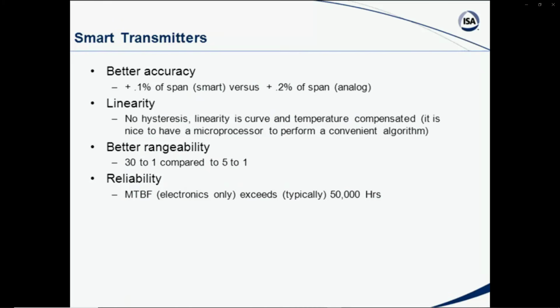At one point in time, we were using the conventional analog transmitters, actually of 1/4, 3/4%, some of them even 1% in some cases, and we were using those and putting that into a highly accurate electronic computer system or some system that had high accuracy. But now with the smart transmitters, we can get even better than 1/10% of span, which is a lot better than the old 1/4 or 1/2% that we used to get.